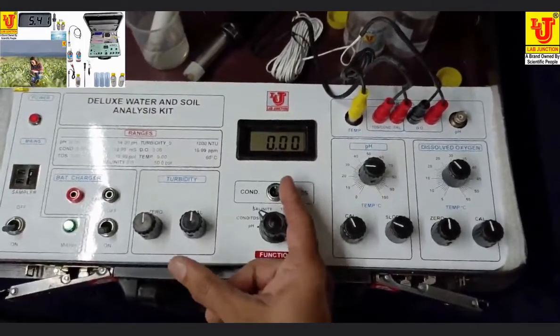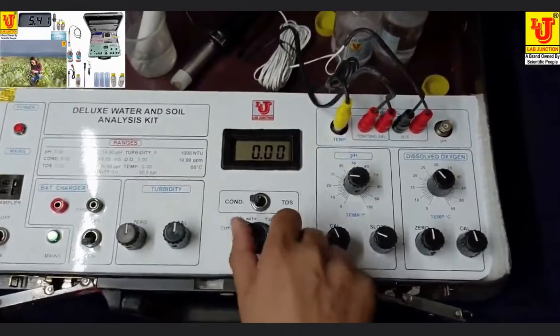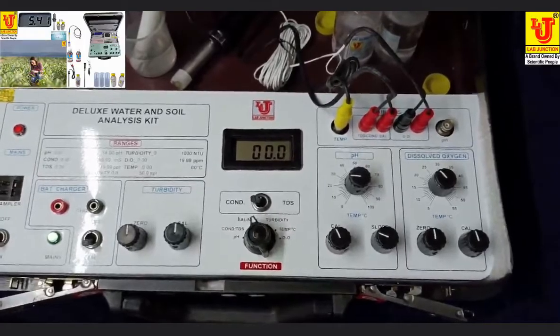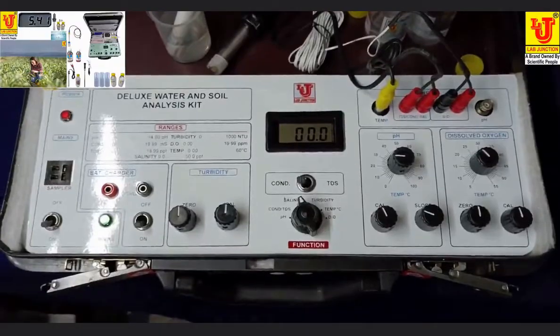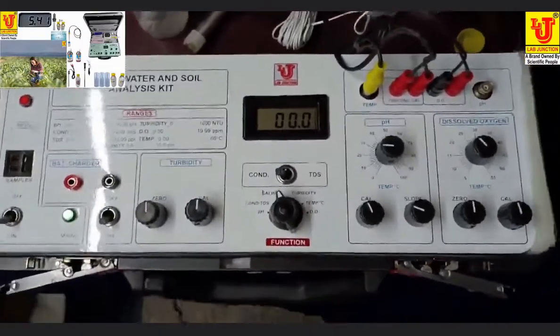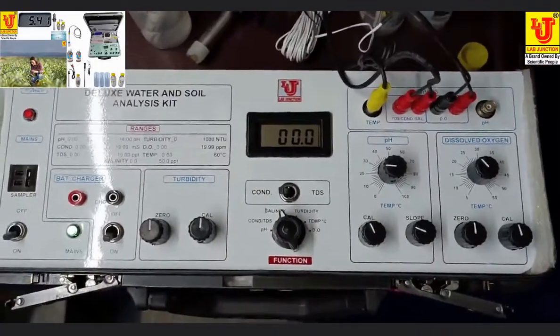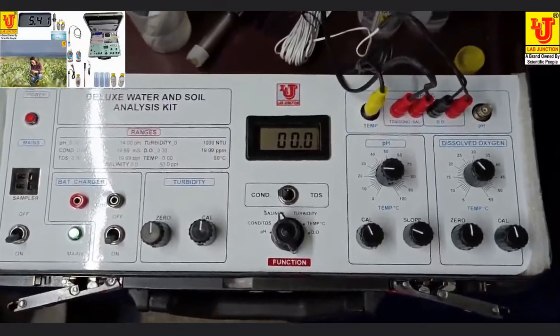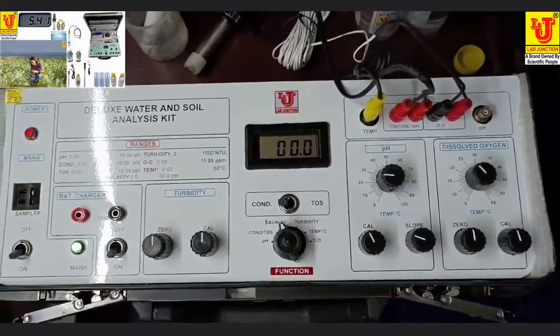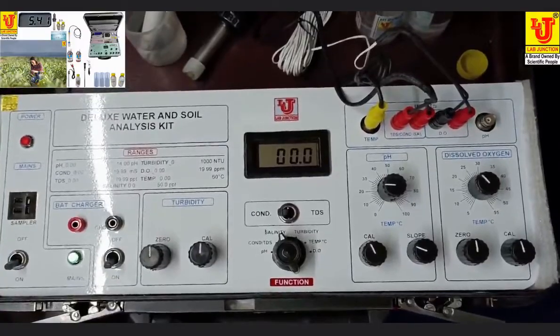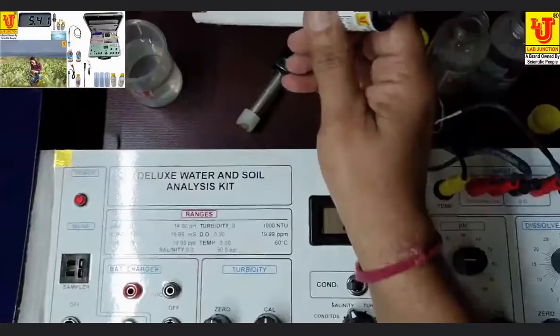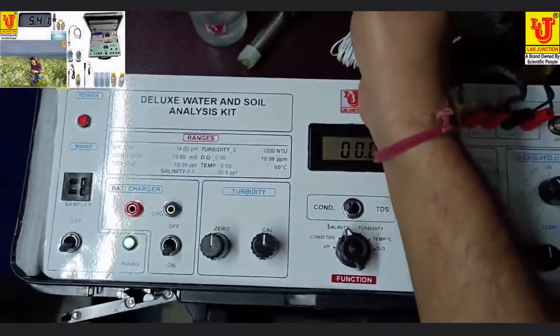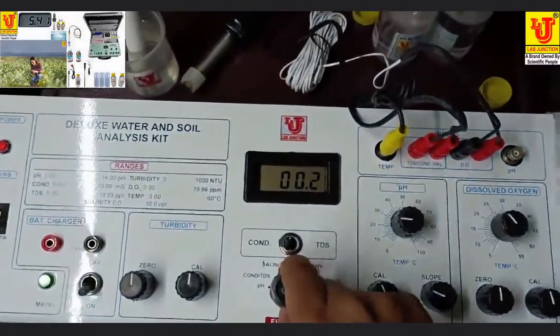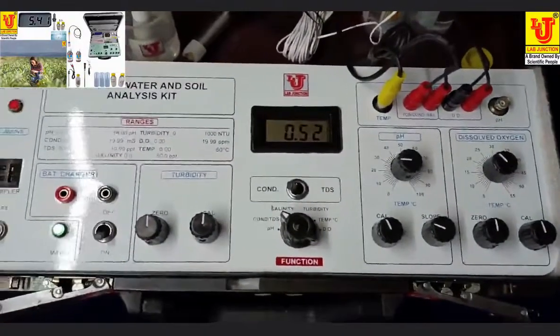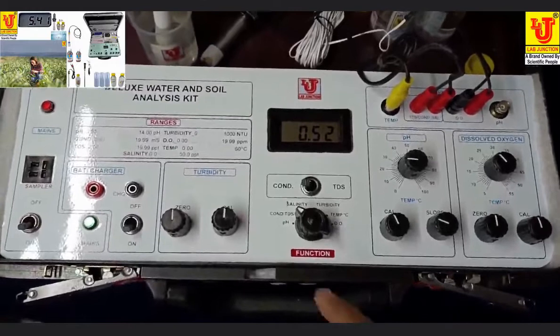When you check salinity, switch this control to conductivity and go to salinity. Then it shows salinity. Suppose you have another sample. Now this is the sample of drinking water. I'm checking its conductivity. Now it's showing the conductivity value directly.